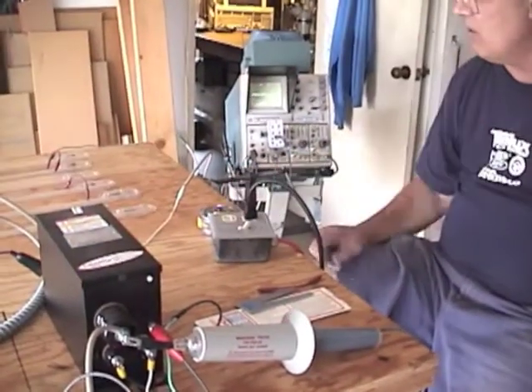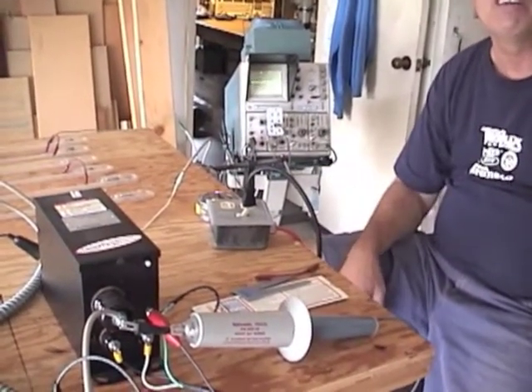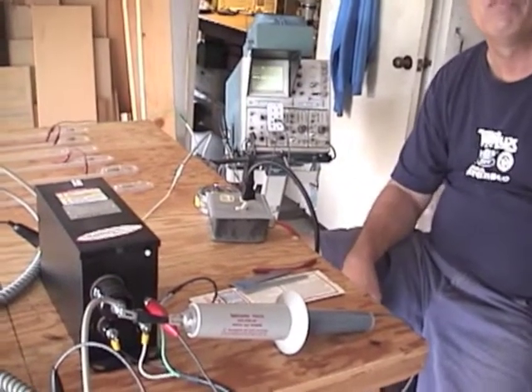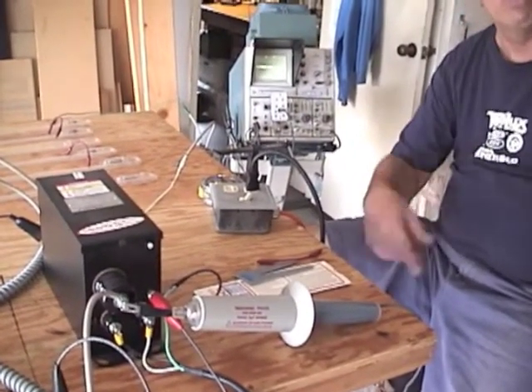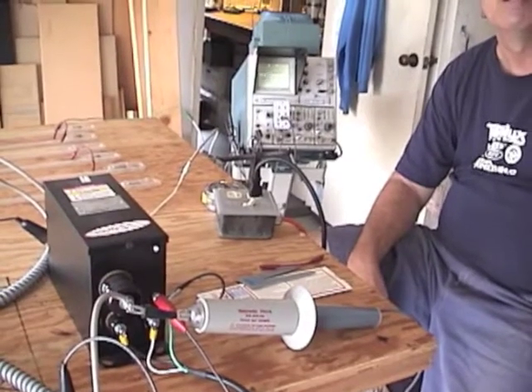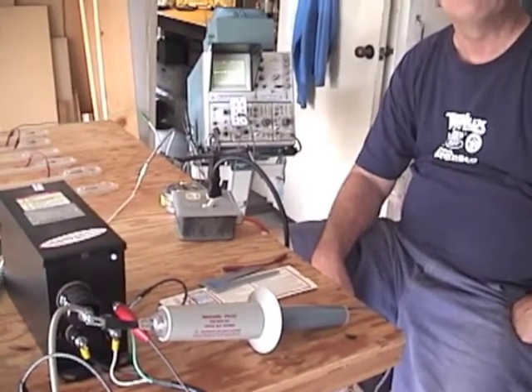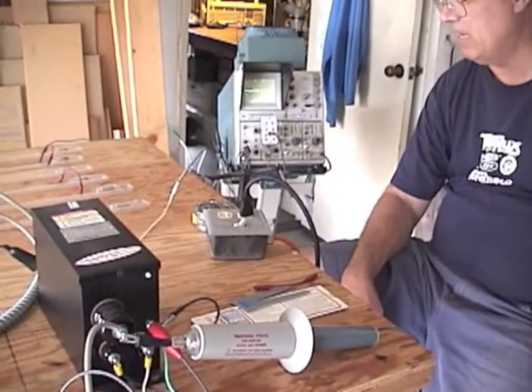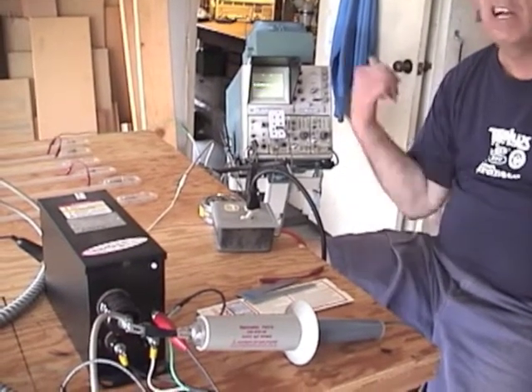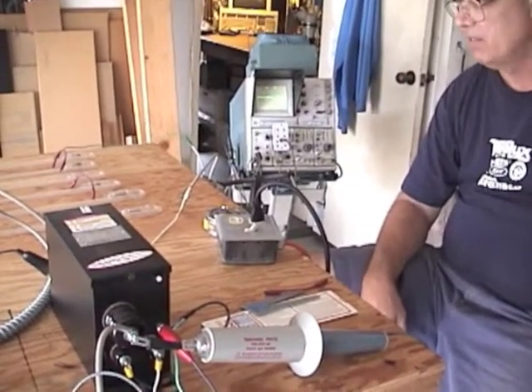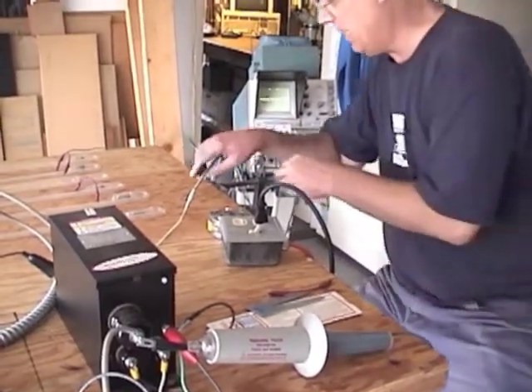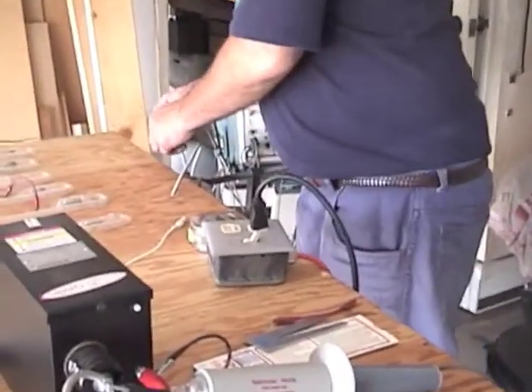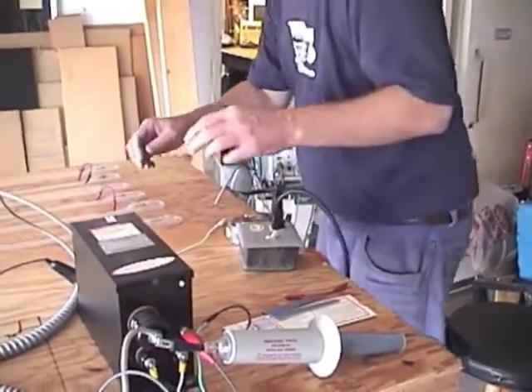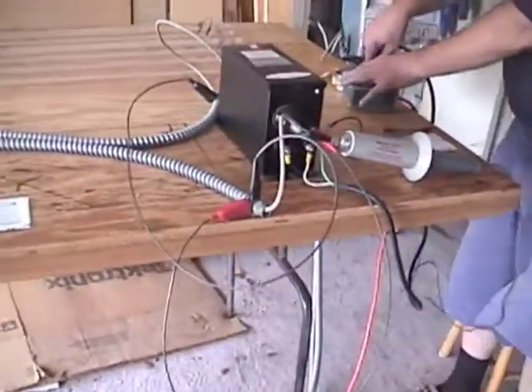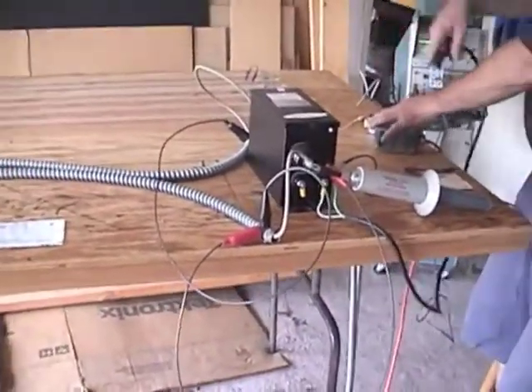So even though our meter is showing that we're properly loaded, in the ballpark, we expect 3,750. That was showing, what did I say, 38? Anyhow, technically we're slightly over. But what it's not showing me is the 10 kV spikes. So let's go back. This is a sanity check. We'll take this back out. Plug that sucker.